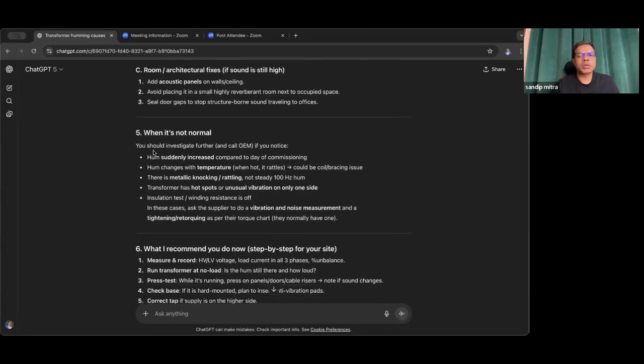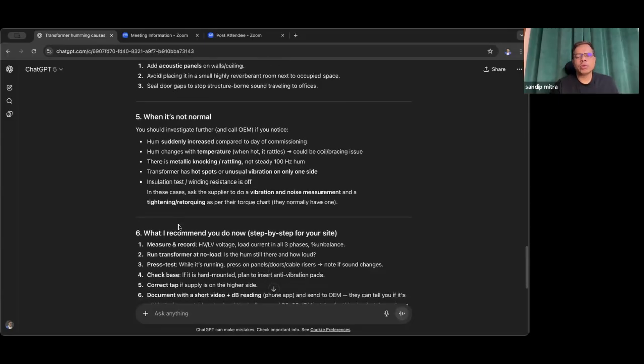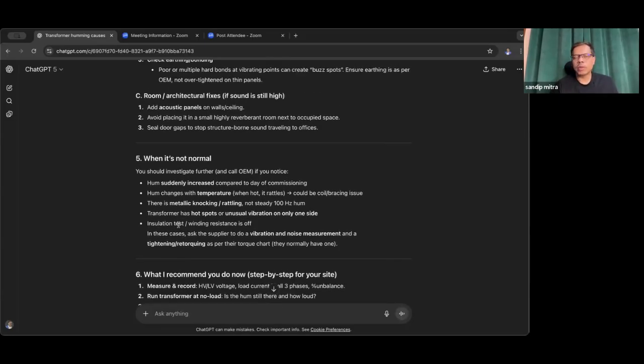Now, when is it not normal? You should investigate further and call your OEM if you notice the hum suddenly increased compared to the day of commissioning, the hum changes with temperature, there is a metallic knocking or rattling, not a steady 100 Hz hum, or the transformer has hot spots or unusual vibration on only one side. Also do an insulation test. So whenever you find this kind of problem, it is better to call the OEM immediately because your system will be under warranty. It is not advisable to touch the transformer by yourself because there will be a warranty clause violation.